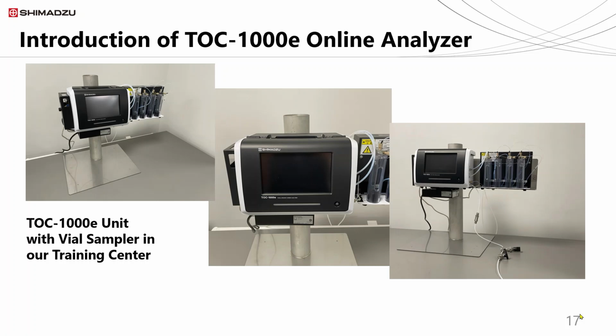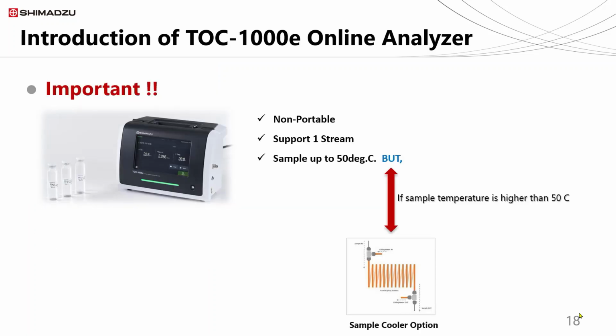Here is the installed unit with Vial Sampler on a pole in our training center. You can see the instruments in both the Shimadzu Istanbul office and the Dubai headquarters training centers. TOC-1000e is not a portable device, and we can connect only one sample line to the device. The online sample temperature should not exceed 50 Celsius degrees. If the sample temperature is higher than 50 Celsius degrees, you need an optional accessory called the sample cooler option, which is also provided by Shimadzu.